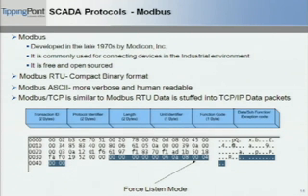Even though you have 2 bytes for length, the maximum allowed length for a Modbus protocol is only 254. So if you see any length byte which is greater than 254 bytes, there itself you can notice that there's an attack or somebody's trying to fudge around with your data. Almost all the queries have a length of only 06. So that's an easy way, if you're writing an IDS kind of a filter or something, you can just mention that the length has to be just 06.